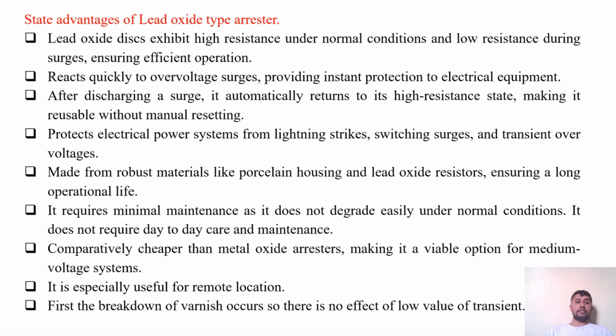State advantages of lead oxide type arrestor. So there are several advantages of lead oxide type arrestor. Some are listed over here. Lead oxide disc exhibits high resistance under normal condition and low resistance during surges, ensuring efficient protection. It reacts quickly to overvoltage surges, providing instant protection to electrical equipment. After discharging the surge, it automatically returns to its high resistance state, making it reusable without manual intervention or resetting.